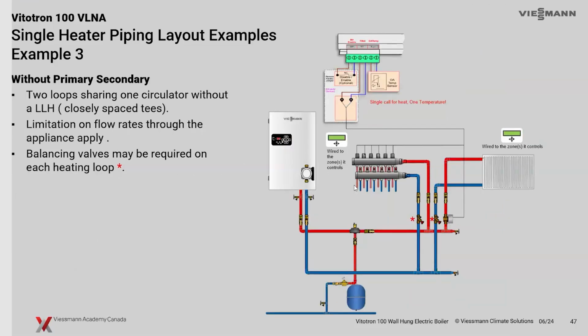All right. So some other ones, if you're doing a two temperature system here, or not just two temperatures, but two different types of heat emitters. It might be around the same temperature. It could be a staple-up radiant system, for instance, and some low temp panel rads. So we're designing for the same temperature. No mixing valves required on the system here.